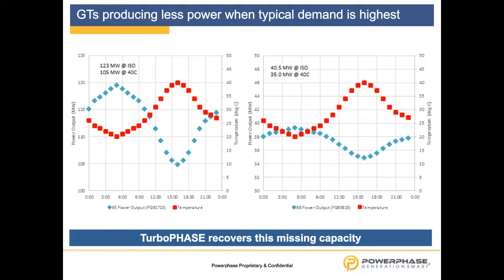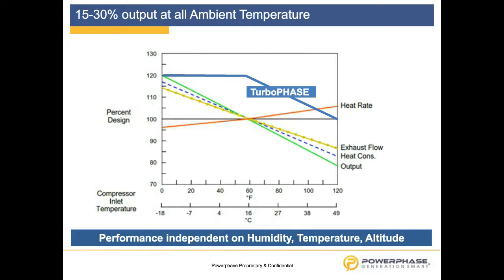And in the next graphic, we see what I just said. The temperature range is on the lower scale, and the percent of the output on the left scale. At around 16 centigrade, each gas turbine has its design capacity, its ISO condition capacity. If we go higher with the temperature, the mass flow and hence the exhaust flow reduces. With it, the output reduces. And by doing that, the efficiency reduces, and the heat rate increases.